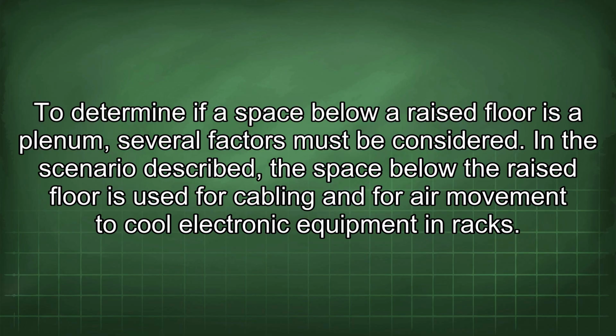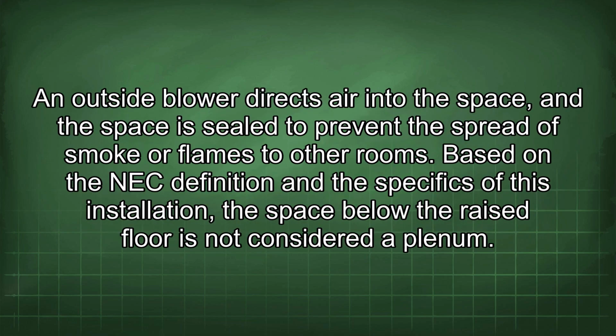In the scenario described, the space below the raised floor is used for cabling and for air movement to cool electronic equipment in racks. An outside blower directs air into the space, and the space is sealed to prevent the spread of smoke or flames to other rooms.